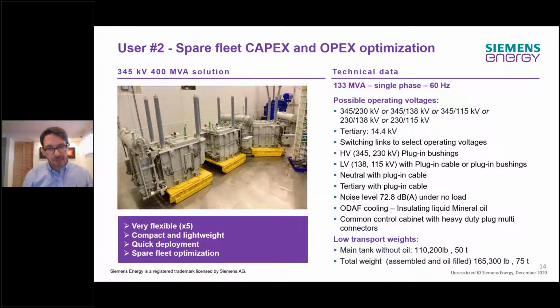User number 2 was this one, and you see there the 3 transformers that are now finished and ready for shipment. Extremely flexible as well, with 5 different voltage levels achieved. It also had a tertiary winding. On the high voltage side, we had plug-in bushings, and on the low voltage, 138 and 115, we had both plug-in cables or plug-in bushings for that added flexibility. Neutrals and tertiary, again, with plug-in cables. This transformer was with mineral oil and also had a common control cabinet.